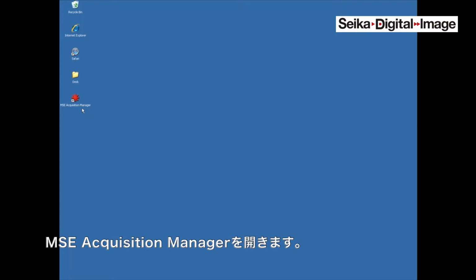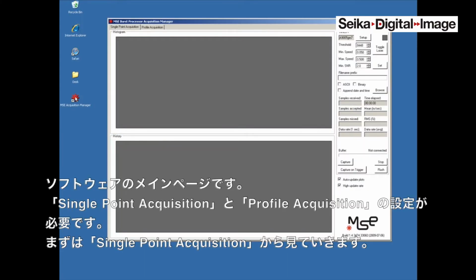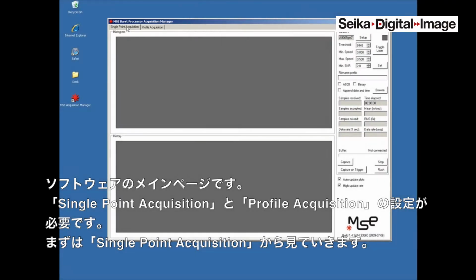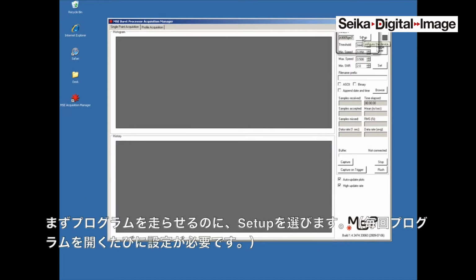To start the program, run Mse Acquisition Manager. This is the main page of the software, and the first thing you need to do is choose between a single point acquisition and a profile acquisition. So we'll start with a single point acquisition. You need to run the setup each time you open the program.